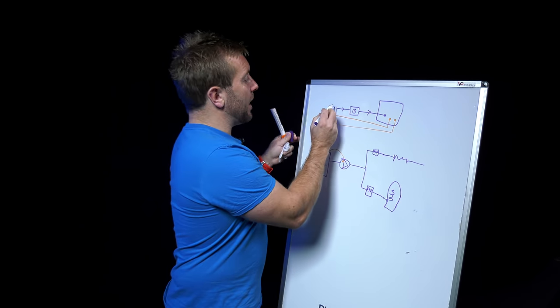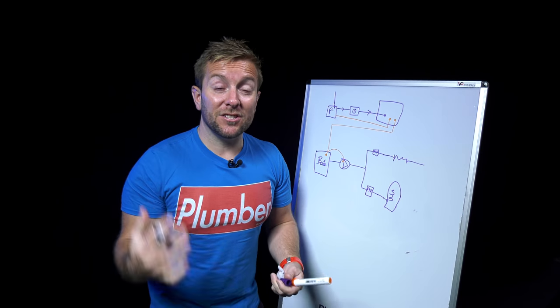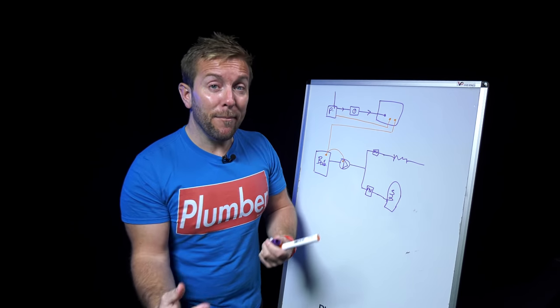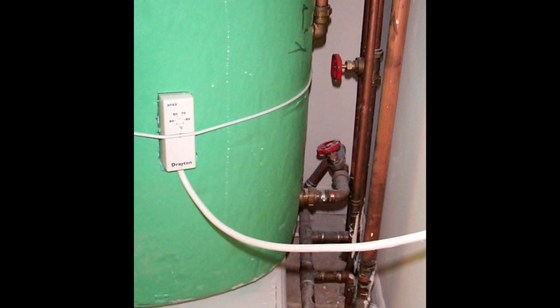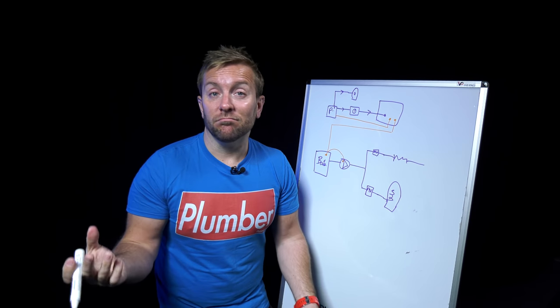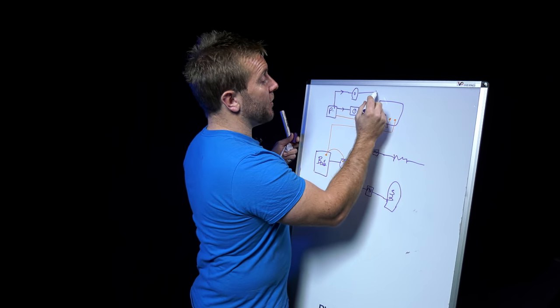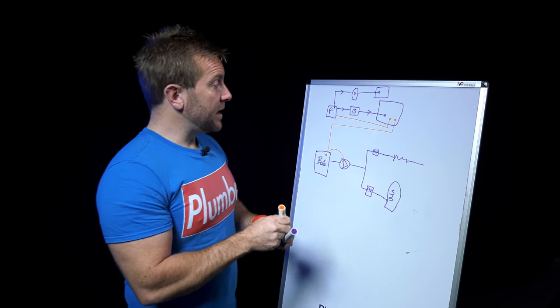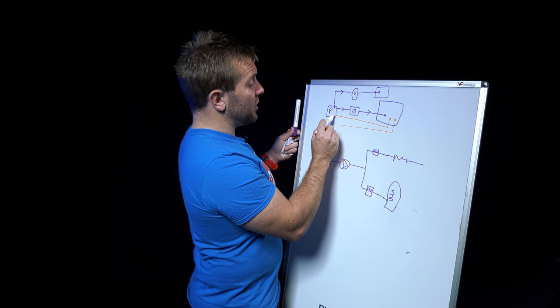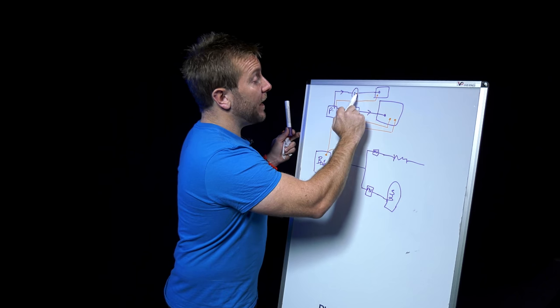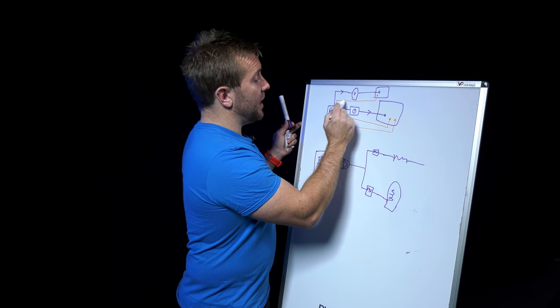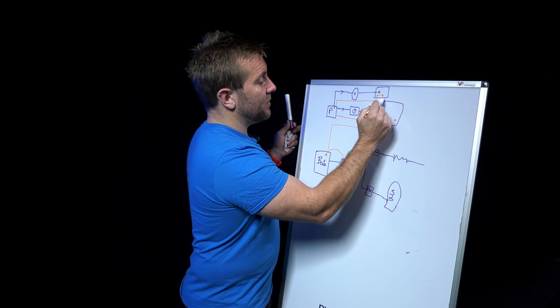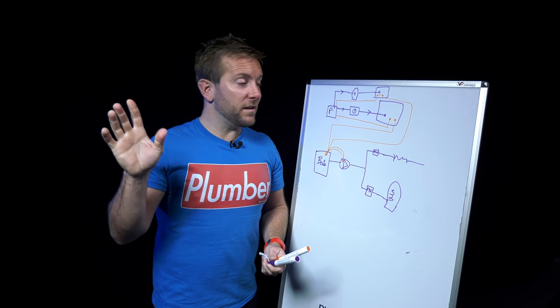Now we need a safe way to tell the boiler and the pump that there's now a need and a demand and it's safe for them to come on and start sending heat around the heating system. The way we do that is we have another supply that comes out of the programmer and it uses a small switch. So looking at this here, this is a three port valve. So we've got our flow coming in, then we've got A and B going out. When this opens up, you can see that that is moving onto those two little bits just there, making an electrical connection, a switch to safely tell our pump and our boiler to come on.